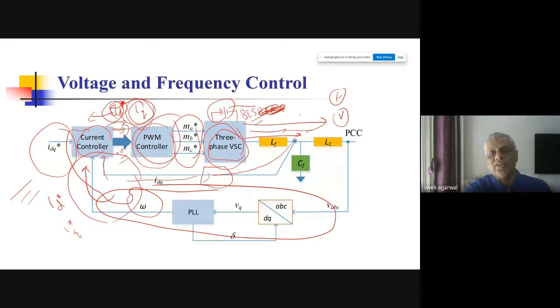Similarly, the voltage will dip when reactive power is drawn. In synchronous generators, if more reactive power is drawn, the terminal voltage falls. So what you do is try to increase the flux, provide more excitation, and shore up that voltage.